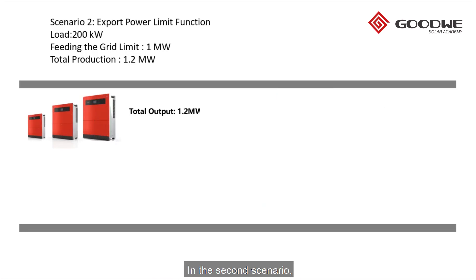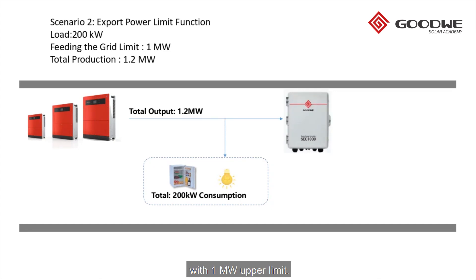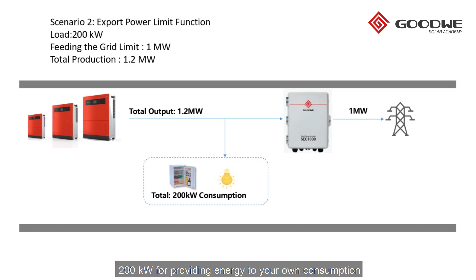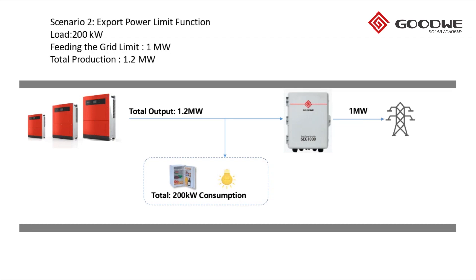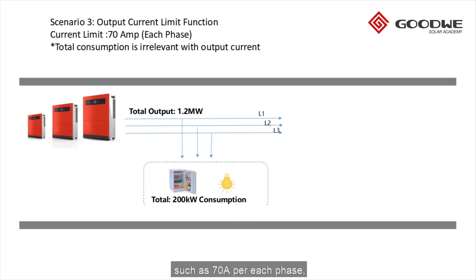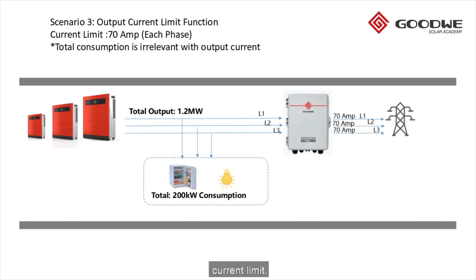In the second scenario, if your local grid company allows you to sell electricity to the grid with a 1 megawatt upper limit, then we have to use the export power limit function and the inverter will produce 1.2 megawatt instead of 1.5 megawatt — 200 kilowatt for your own consumption and 1 megawatt directly going to the grid. In the third scenario, if you have an output current limit such as 70 amps per each phase, then the inverter will reduce the output current in accordance with your output current limit.